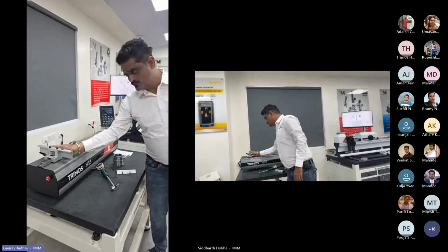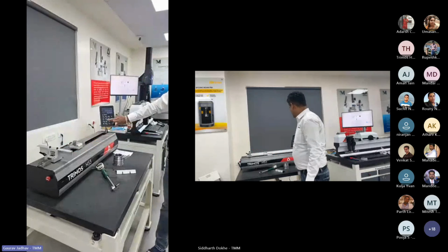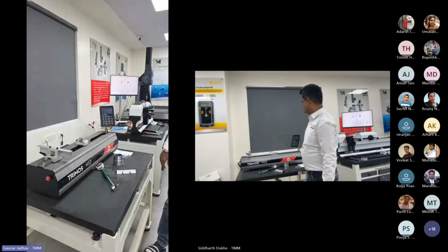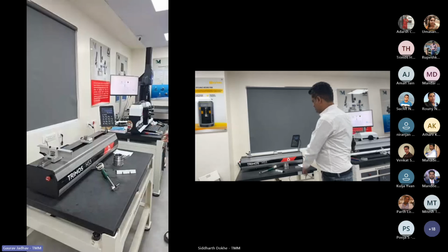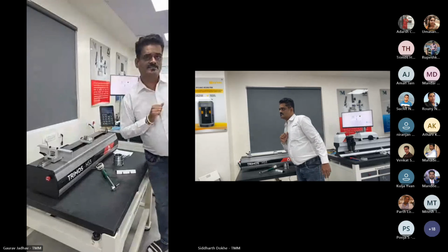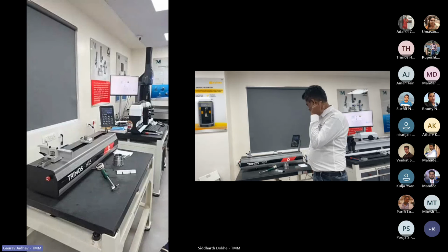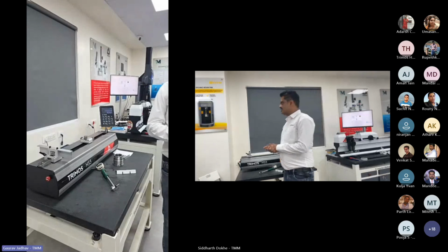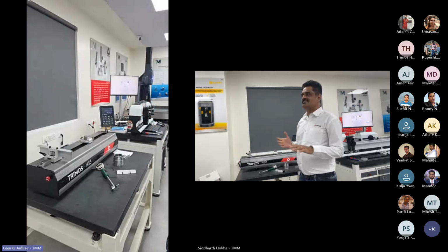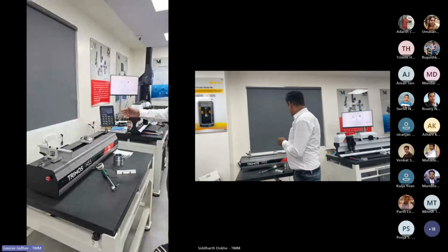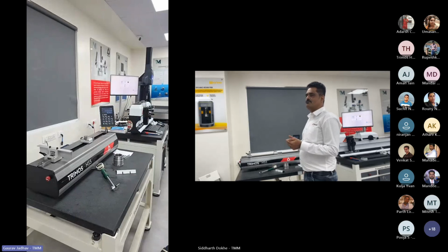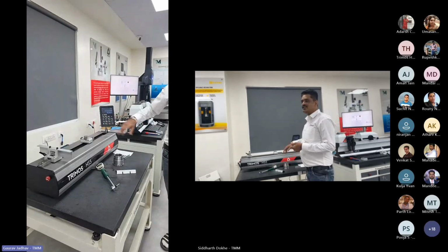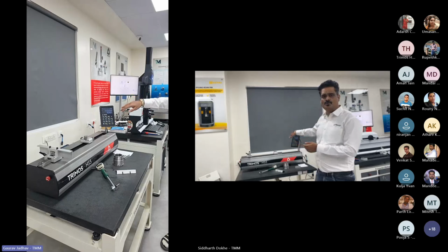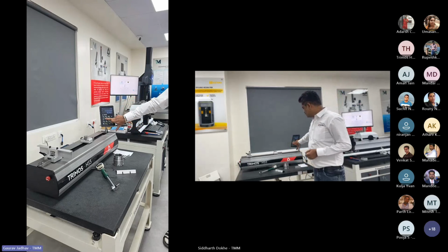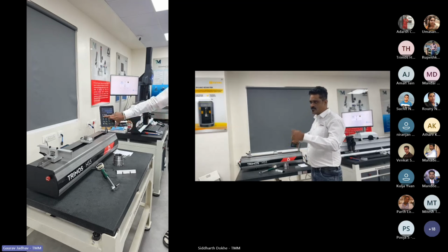So you can mount this bigger plate. So you can go straight away to 350 if you want to set a bigger bore gauge. Just say enter. The machine will go to 350 and stop. You can set the bore gauge very easily. Again, if you have some repeated sizes, then this display is having memory of 8 readings. So you can save 8 different readings in this display, which is frequently used, and that you can recall easily. So no need to input these values again. So if you want a different size which is already set up, just you have to press this 7 number key.